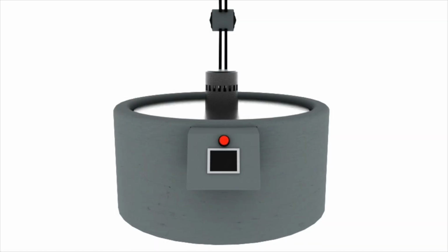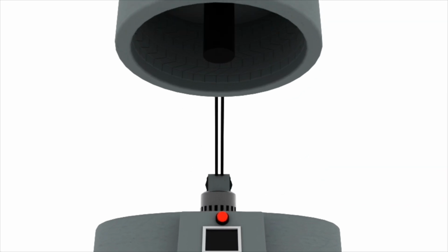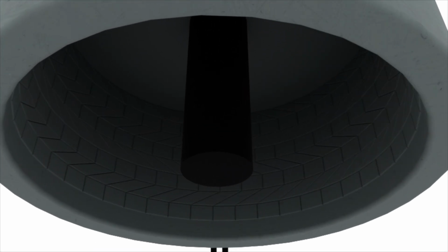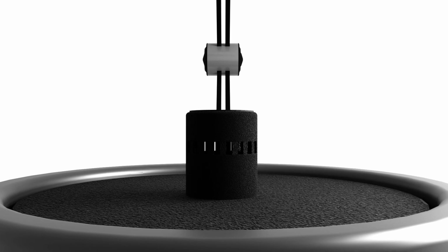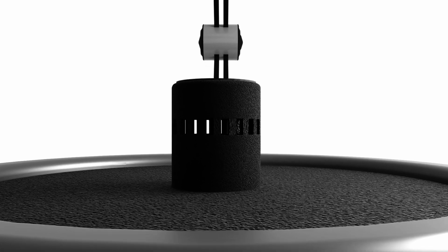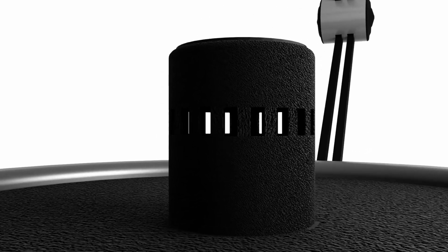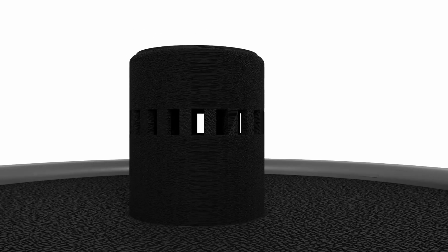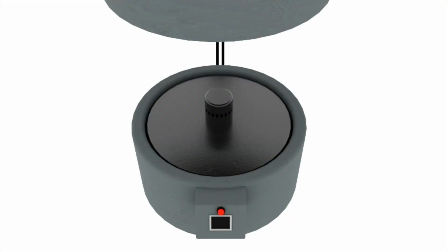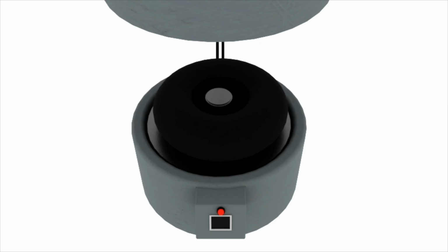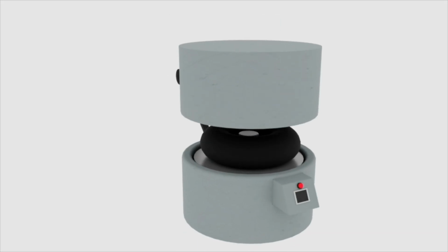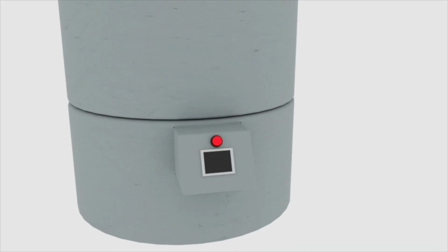The temperature of saturated steam is directly related to its pressure. Using a steam pressure regulator and closed loop control eliminates the need for PID tuning, offers tighter control, and results in less temperature drift. Simply put, if you control the pressure of saturated steam, you can control the temperature.